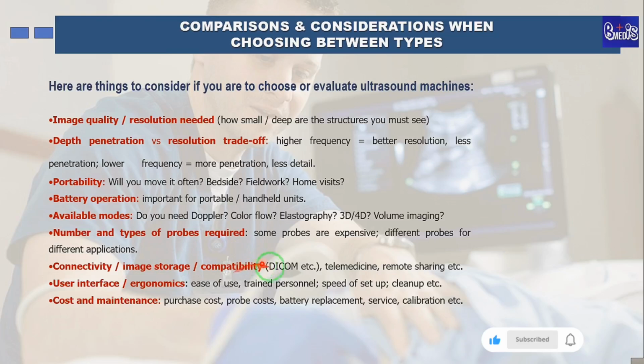Connectivity, image storage and compatibility. For instance, DICOM compatible, telemedicine, remote sharing. Now, modern ultrasound machines come with these modern features where after your scan, you can send your images online to any location because of the current applications that are embedded in most of these new machines, which the older ones don't usually come with. Then the user interface and ergonomics, ease of use, trained personnel, speed of setup, cleanup, etc. There are some ultrasound machines that come with very user-friendly interfaces which make your scan procedure very, very easy. Then we have cost and maintenance, purchase cost, probe cost, battery replacement, service and calibration. So you also need to put all of this into consideration when considering the machine you want to purchase. There are some machines that are easy to maintain due to availability of parts and engineers.